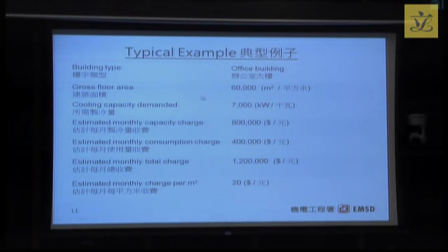Let me give you a typical example for your reference. There is an office building with gross floor area around 60,000 square meters, and cooling capacity demand around 7,000 kilowatt. Based on the formula mentioned, the estimated monthly capacity charge is around $800,000, and the estimated monthly consumption charge is $400,000. So the total charge per month is $1.2 million, and the estimated monthly charge per square meter is $20.